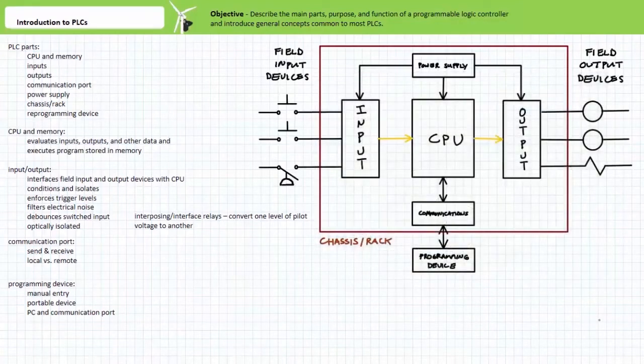As the name implies, an interposing relay simply interfaces the two different voltage schemes. Input and output signals are conditioned by the input and output modules by enforcing minimum trigger levels, filtering electrical noise, and debouncing switched input.